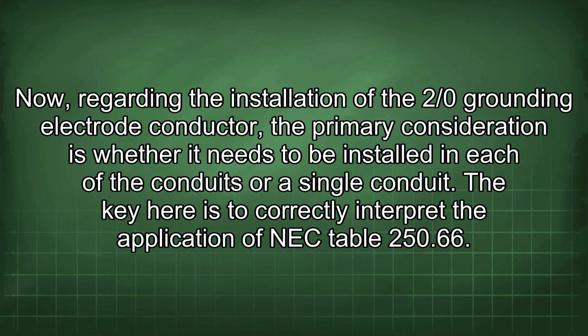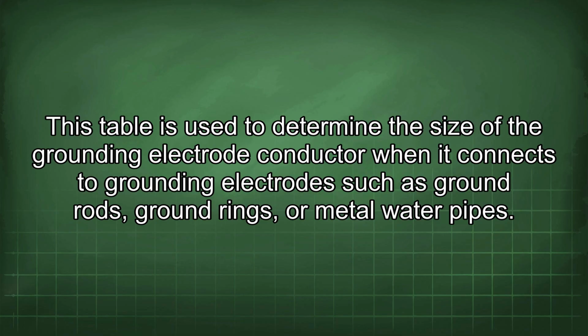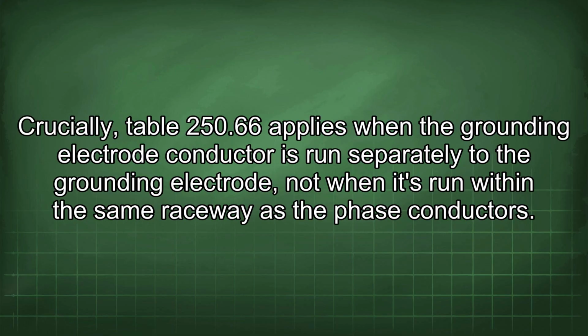Now, regarding the installation of the 2/0 grounding electrode conductor, the primary consideration is whether it needs to be installed in each of the conduits or a single conduit. The key here is to correctly interpret the application of NEC Table 250.66. This table is used to determine the size of the grounding electrode conductor where it connects to grounding electrodes such as ground rods, ground rings, or metal water pipes. Crucially, Table 250.66 applies when the grounding electrode conductor is run separately to the grounding electrode, not when it's run within the same raceway as the phase conductors.